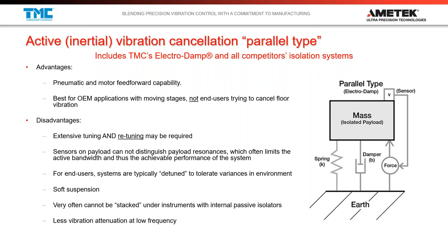But one of the main disadvantages of these systems is that they're soft spring based. And the soft spring, as I mentioned before, is always going to have a 2 hertz resonance or somewhere in that low frequency range. So if you picture a vibration coming up from the earth and going into the payload, then that vibration at 2 hertz is going to be sensed by the sensor and it's going to want to cancel it out. That's fine. But we're talking about amplified vibration at low frequency.